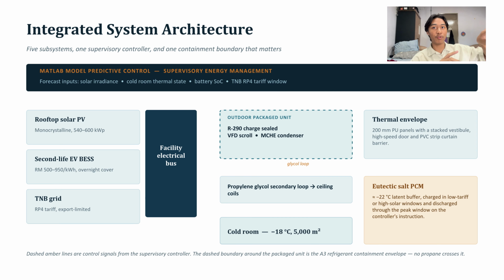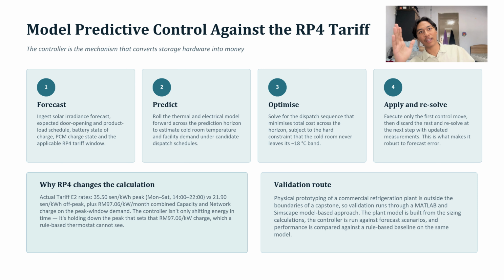You can see the dashed boundary around the outdoor package unit. This is the containment boundary Hamid described before, where the R290 stays sealed in there. Only the glycol loop, carrying the non-flammable refrigerant, crosses into the cold room, right? On the right, you can see the PCM, the phase change material, which acts as a thermal battery at around negative 22 degrees. It charges when energy is cheap and solar is abundant, and also discharges to help cover the expensive tariff window.